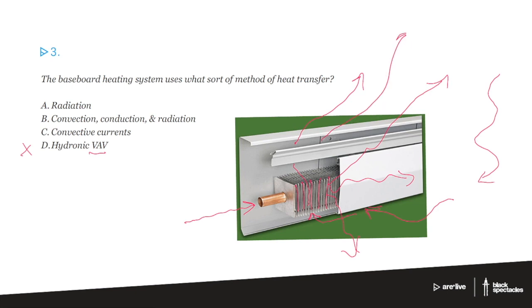So this is a radiator that also has convective currents. So essentially what's happening here is I have convection with the hydronic element. I have conduction between the pipe and the fins. I have radiation happening from the fins out to the space. It's radiating from one body to another, i.e. these fins to you as a body. And then I also have convective current, which is another example of convection of air moving up through the system and then washing the wall above it with a heat blanket.